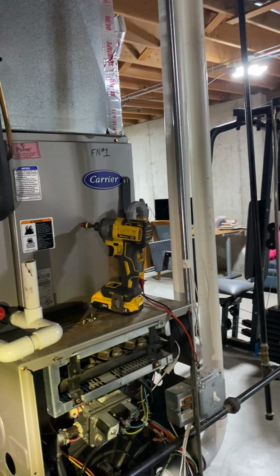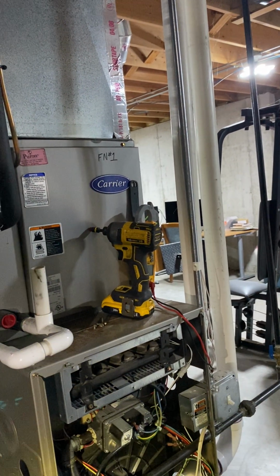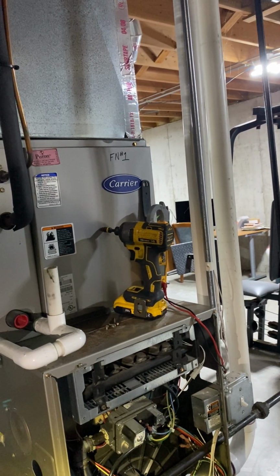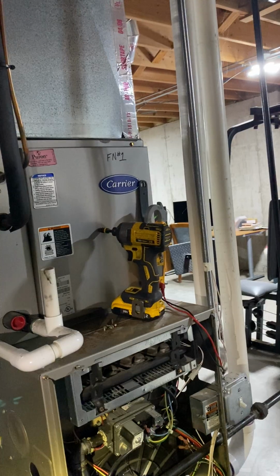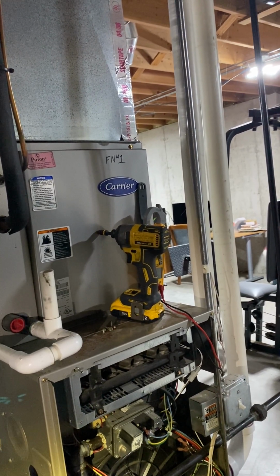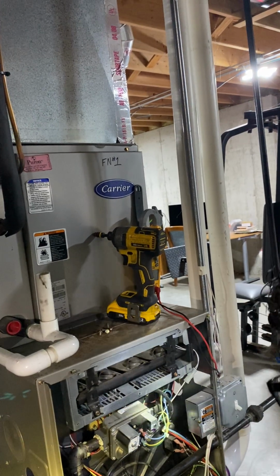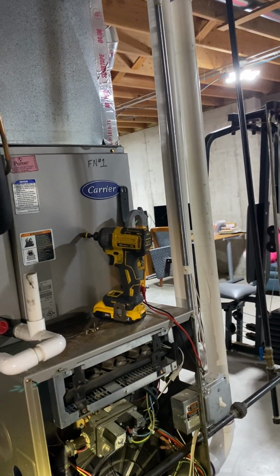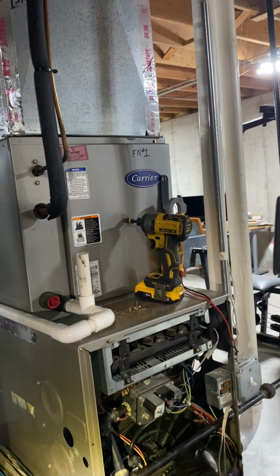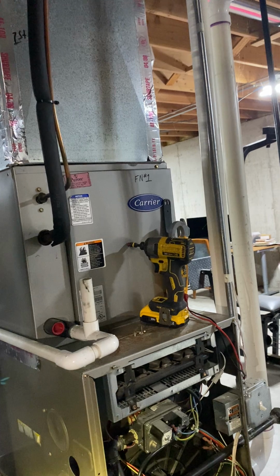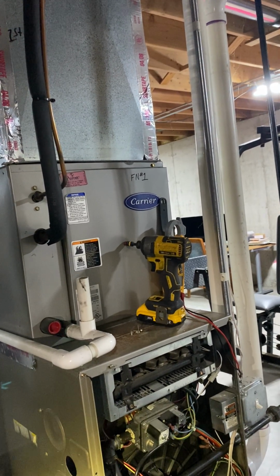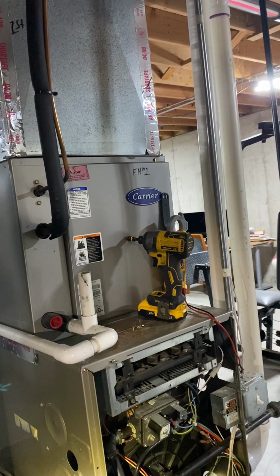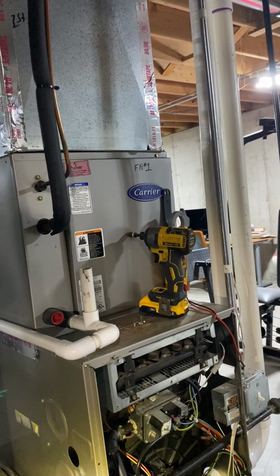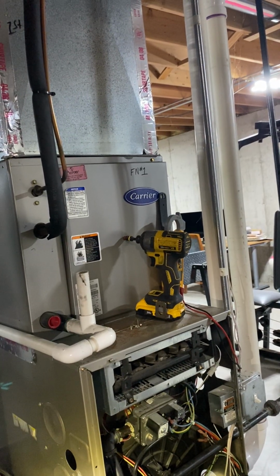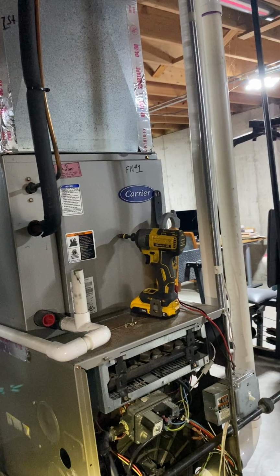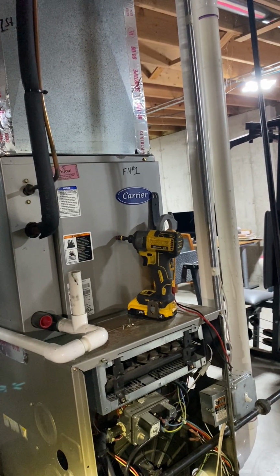How did the water get in? Probably because of a dirty P-trap. Because this is a high efficiency furnace, furnaces should be on yearly maintenance. If you go years without maintenance, it can become clogged with debris. Also, when furnaces get this age, the heat exchanger inside corrodes a lot, and the condensation that goes through that corrosion will get stuck in here and create a clog. So what I want to do is get this clog cleared out, get it up and running. I'll perform testing, I'll do a combustion test to make sure it's running safely and efficiently, and then go from there. But in order to get this thing on and running, I have to clear out all that water.